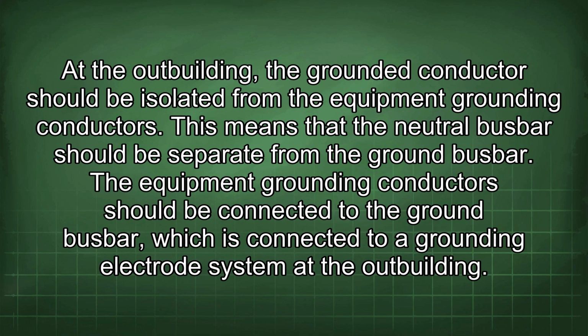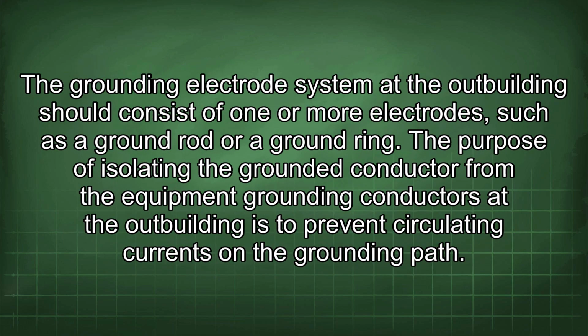At the outbuilding, the grounded conductor should be isolated from the equipment grounding conductors. This means that the neutral busbar should be separate from the ground busbar. The equipment grounding conductors should be connected to the ground busbar, which is connected to a grounding electrode system at the outbuilding. The grounding electrode system at the outbuilding should consist of one or more electrodes, such as a ground rod or a ground ring.